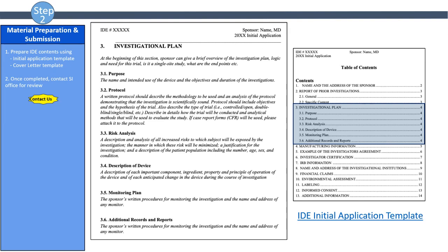Investigational plan brings out the critical details on how the investigations are going to be undertaken using the device. The study protocol provides the critical information needed here, as in INDs. The format will be an expanded protocol summary, since a full protocol will be accompanying the application. The investigational plan may also need a detailed statement on any anticipated safety concerns associated with the device use.